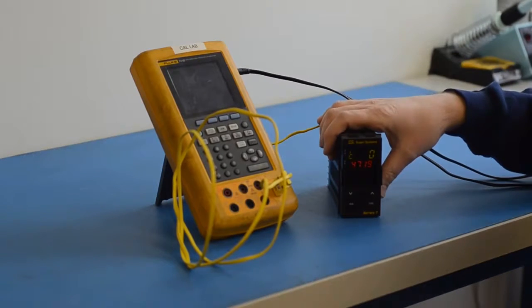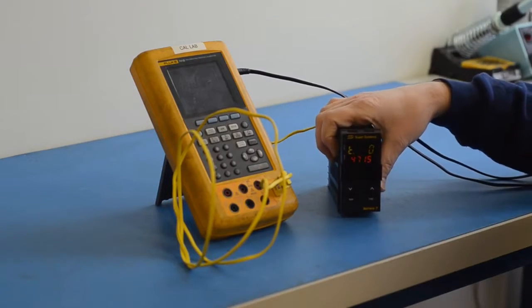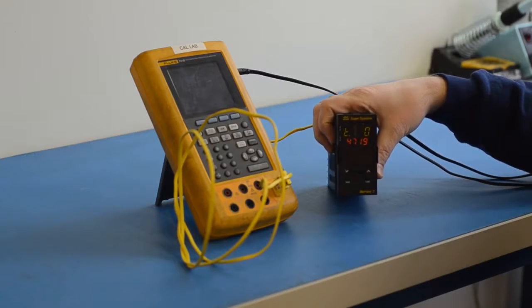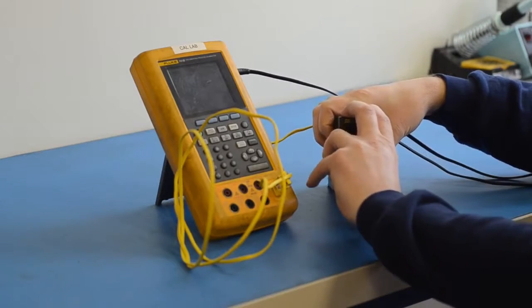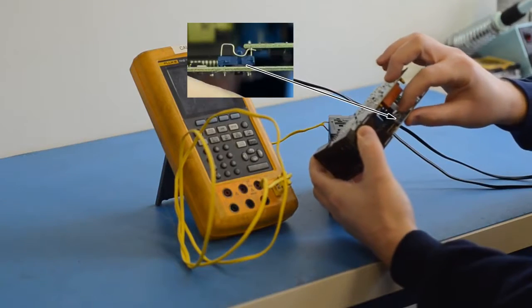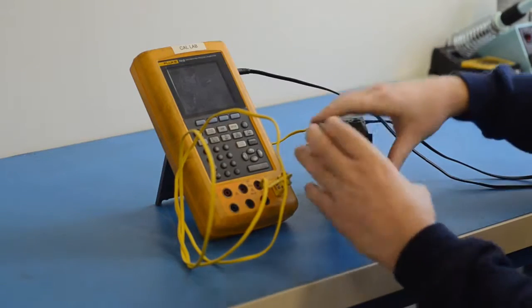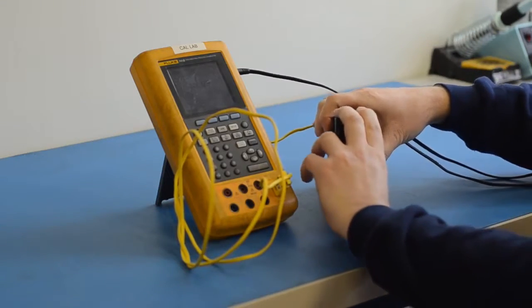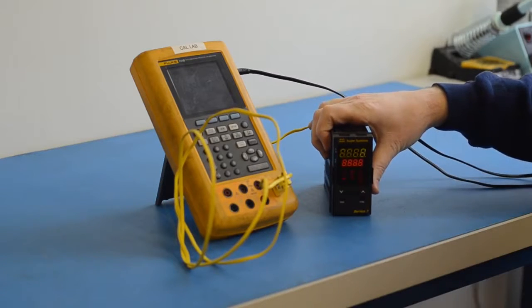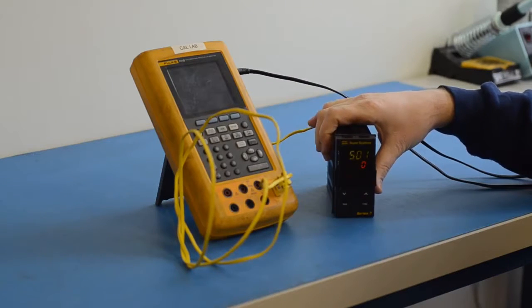So once zero and span calibration is complete, we're going to check the cold junction calibration or adjustment. We have to remove the instrument from its case, relatch our jumper to put it back into operation mode, reinsert it into the case, and this will then start reading the temperature.